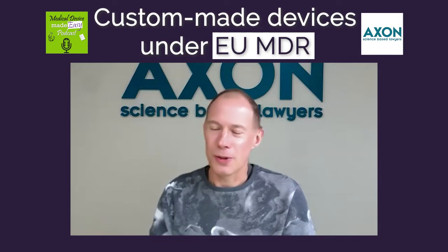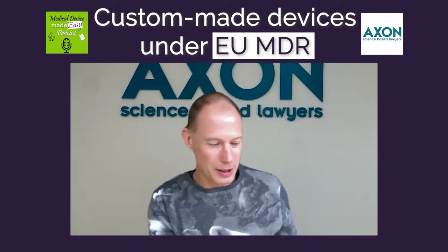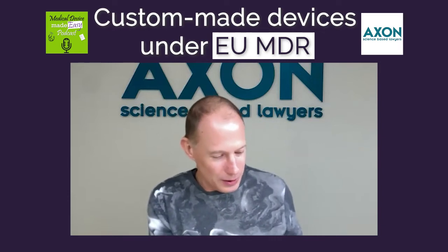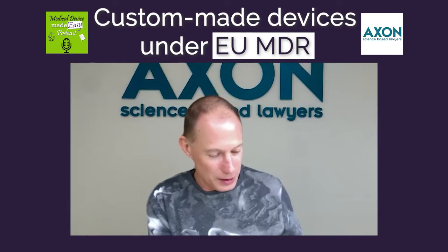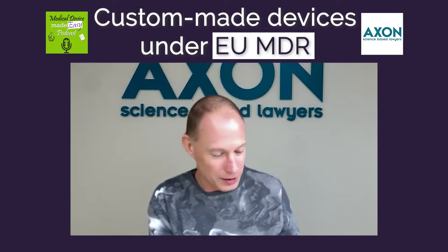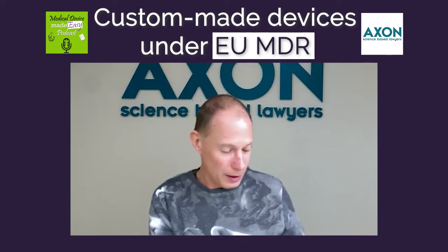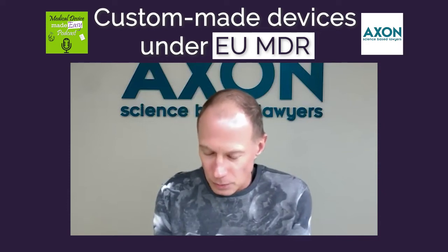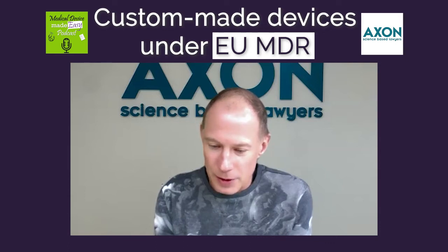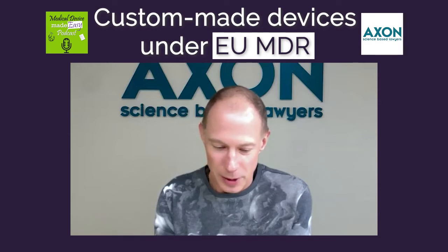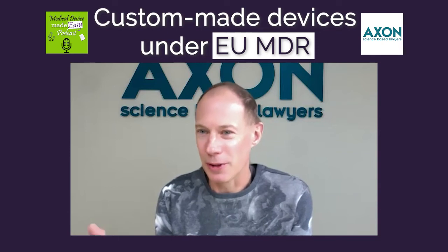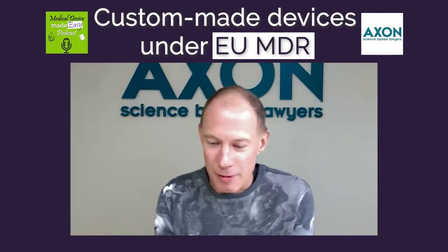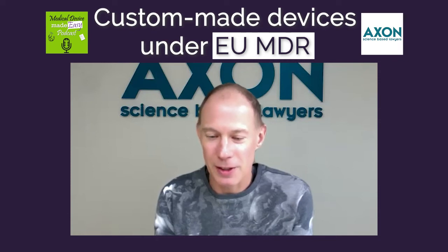PRRC, Article 15, that's also applicable for custom-made devices. And there is something interesting indeed with the custom-made devices PRRC, because it has different qualification requirements. The difference is that the PRRC for a custom-made device may demonstrate the requisite expertise referred to in the first subparagraph by having at least 2 years of professional experience, and now here it comes, within a relevant field of manufacturing.